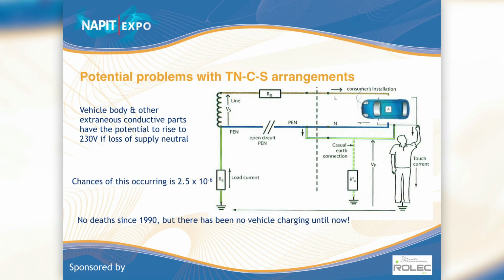Here's your problem with your TNCS. A TNCS system on that side there, at the transformer side, is connected to the star point, your earthing system, and at the consumer side, the neutral and the earth becomes one. Only the supply authorities can join neutral and earth together. We cannot. Ours must be separate across here, but they join it at the cutout. If they have a break in the neutral there, then all of our earthing conductor becomes the neutral conductor. We can actually get a shock between our car body and the earth below us.